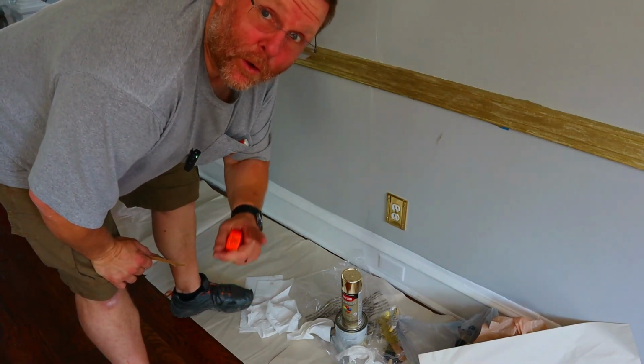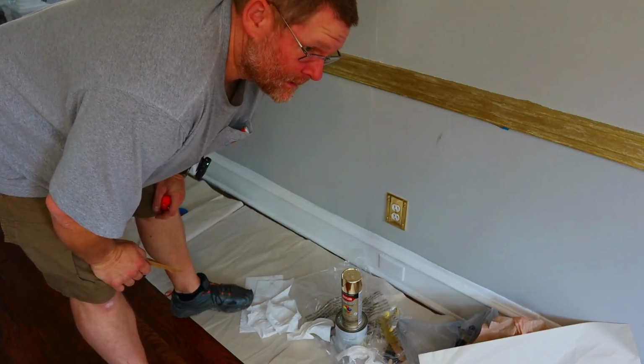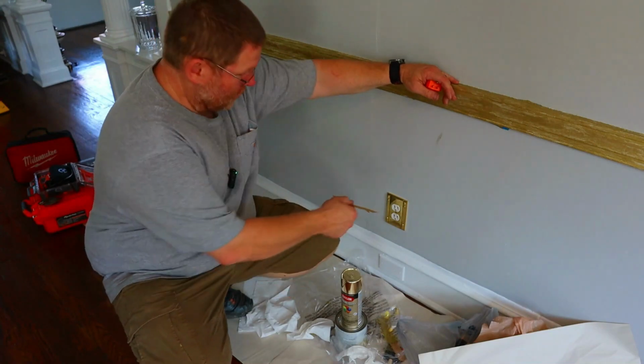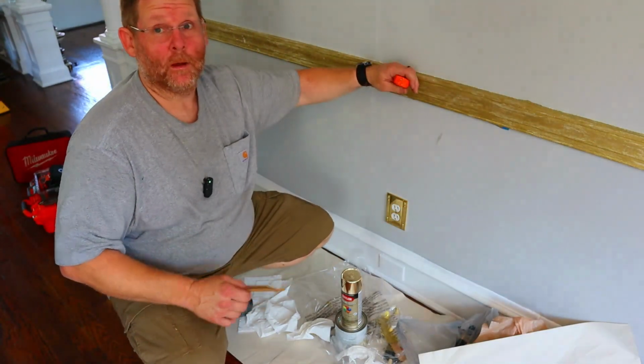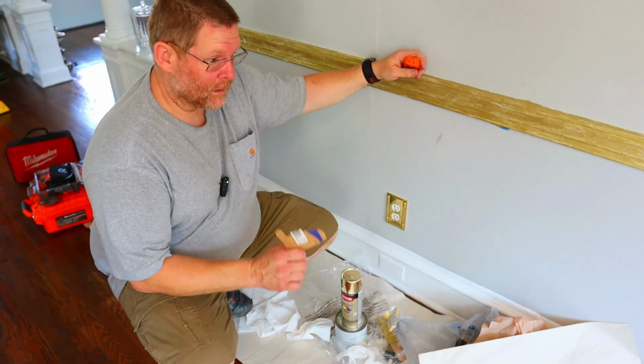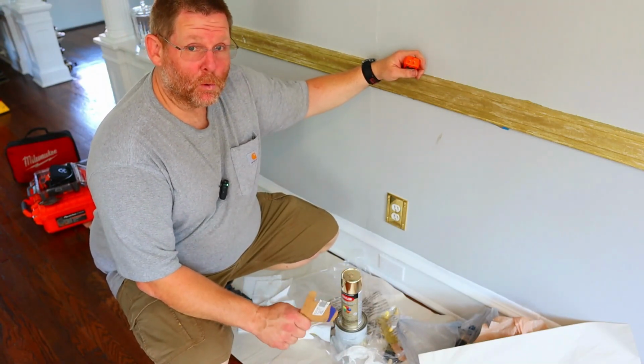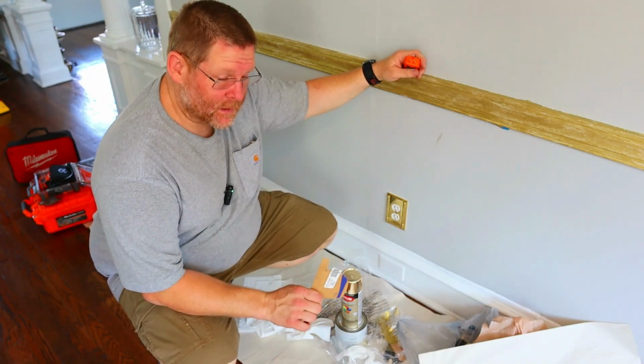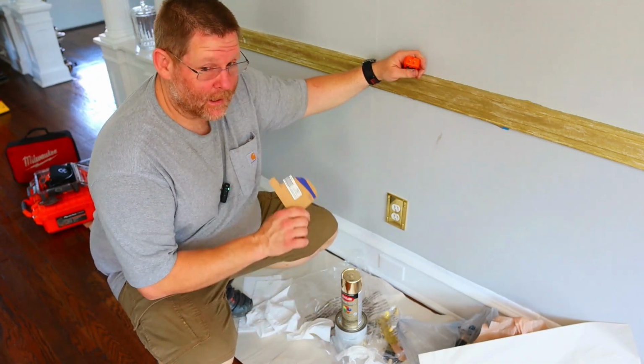Well, you have to stay tuned to the whole video to figure out how to fix this. You can't just put a duplex receptacle in here like this when there's no ground. That is against code, 100%. I got a video, well, luckily this didn't happen here, about a bootleg ground. You do not want to have that on any receptacles.